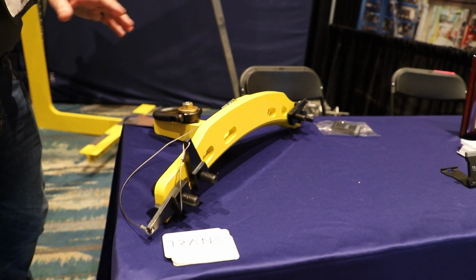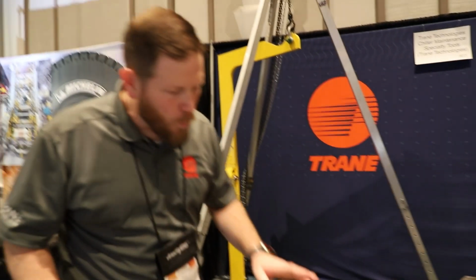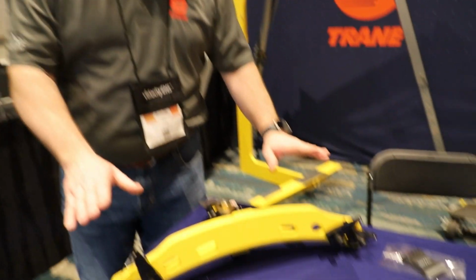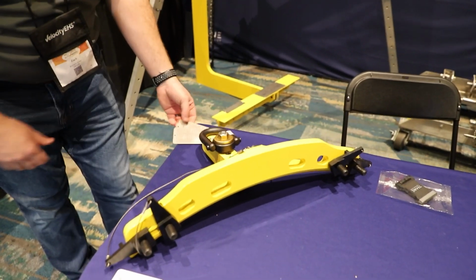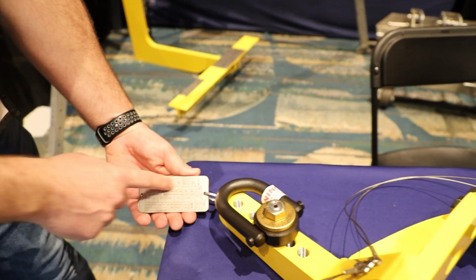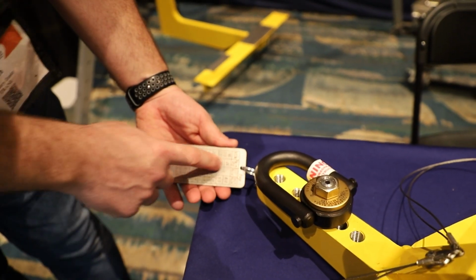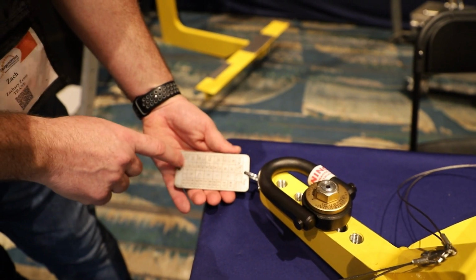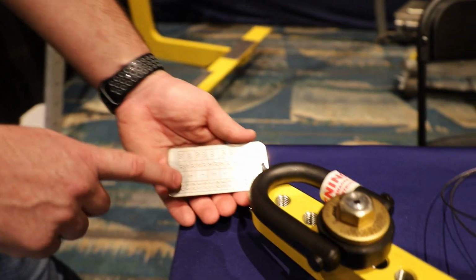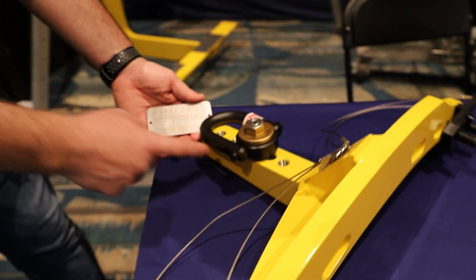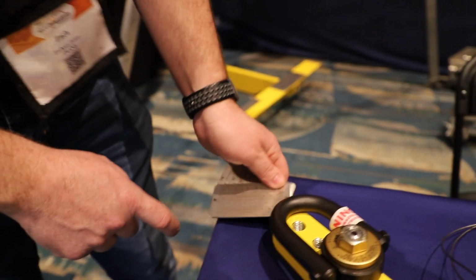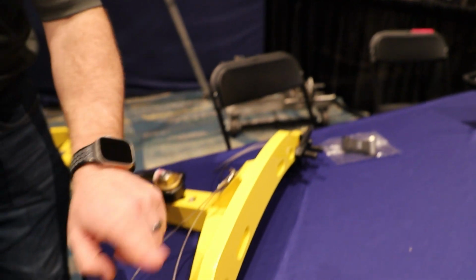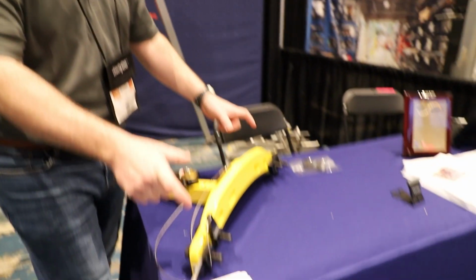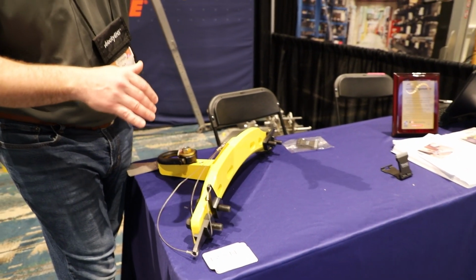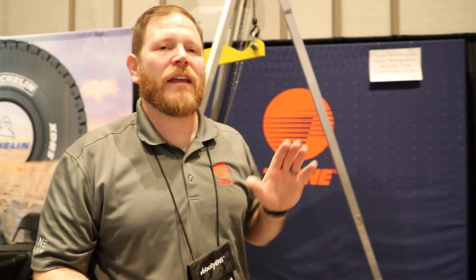This tool is designed to bolt up directly to all suction covers within Trane's centrifugal fleet, so it's multi-purpose—one tool fits every single one. When they bolt this tool directly to the suction cover, they have a tag here they can utilize. It has the tonnage of any chiller they may encounter, and it gives them the number of holes on the suction cover. So if I had a 300-ton chiller, I would utilize lift hole B, that's on this side here, and then holes 4 and 14. As a technician in the field, that tells me I can bolt this directly to that suction cover utilizing those points.